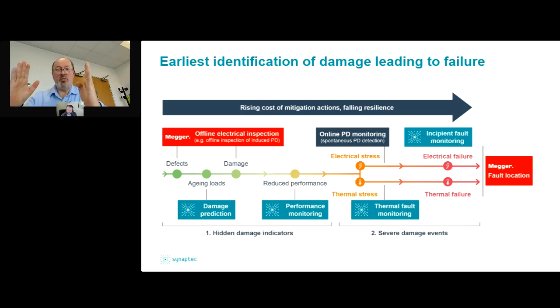So what Synaptec technology is doing, and what Greenlight specifically is there to do, is to fill the gap between these static offline test events and see, well, what is that trend? Is it degrading as we planned, or is it worse than we planned, or are we actually doing better than we planned? And day to day, can we optimize the number of visits and inspections and checks that need to be undertaken to maintain that availability and high performance? And again, Stephen mentioned this, but if you do need to dynamically rate this cable and push it a bit harder sometimes for certain reasons, that's really important, because you've got the ability to optimize that yield, that capacity, but safely without endangering the future longevity of the asset. So all of these day-to-day operational parameters become more visible and controllable between these enormous and expensive scheduled outage events, which typically for a high voltage cable could be anywhere from 5 to 10 days.